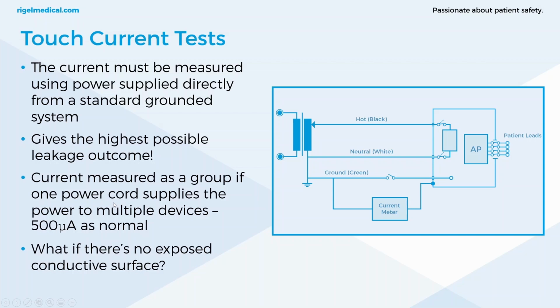Now, comparing this to other standards I've looked at, it avoids quite a bit of confusion when testing things like stack systems. So in NFPA 99 it states that if a fault were to occur with the ground connection in the power cord, then the sum of all those currents from each individual device would flow to earth via any contact with the chassis. So it recommends that the touch current is just measured as a group, and the limit is 500 microamps as normal.